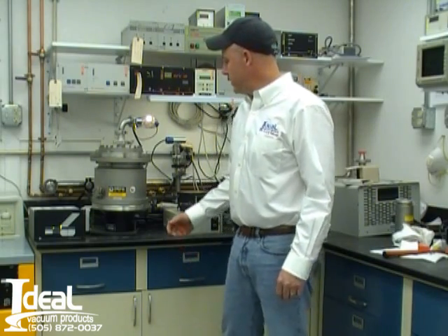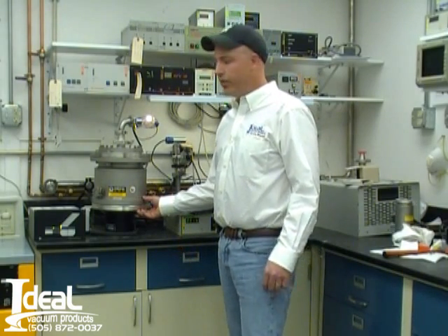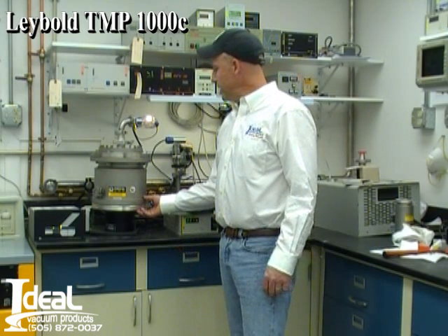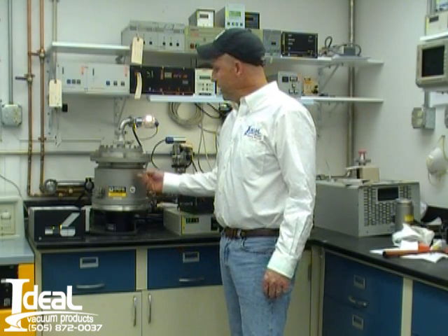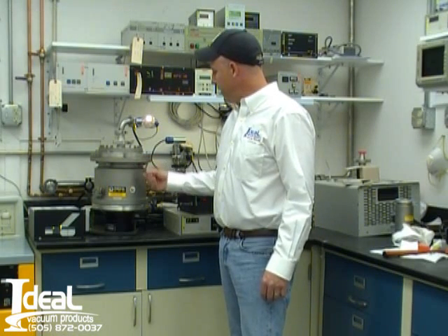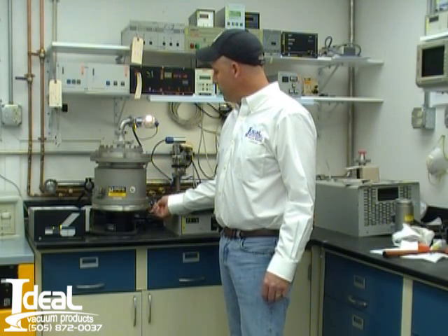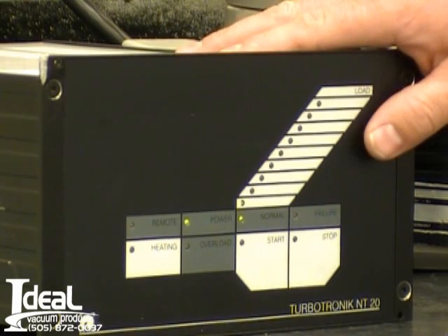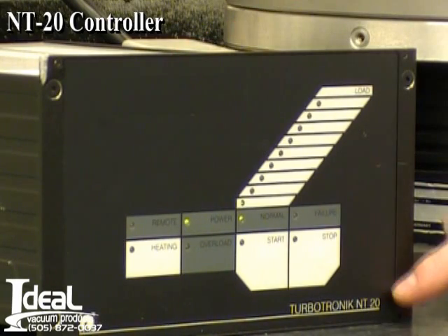I'm Tony Smith with Ideal Vacuum Products, and today we're selling a good used Leybold TMP-1000C turbo molecular pump. The inlet flange is an ISO or ASA 6-inch inlet flange. It's a water-cooled turbo pump with a KF40 exhaust. The controller that goes with this system is an NT20 controller.